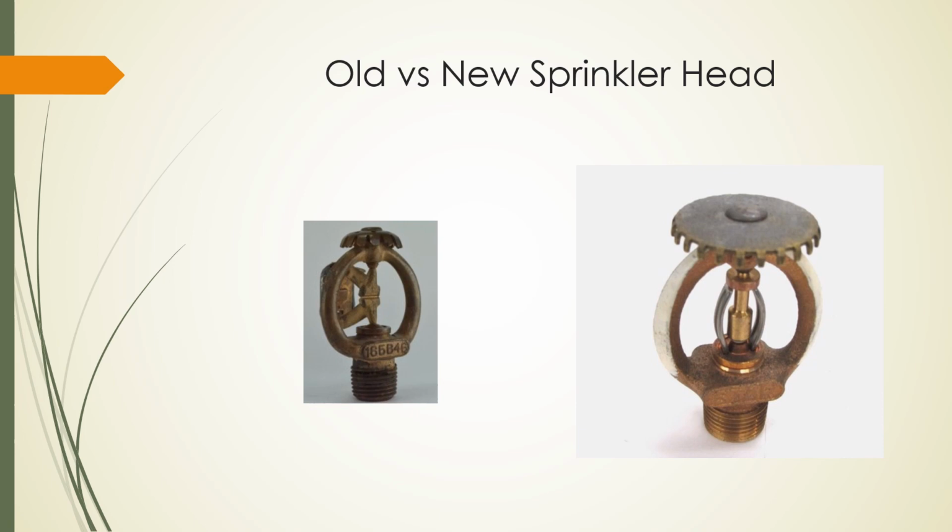So as you can see, there are two sprinkler heads. The one on the left is a 1946 upright star half-inch K 5.6 head. You'll notice that the deflector at the top looks very small. And to the right is a star upright head, date unknown. But you can see clearly that the frame itself looks similar. The fusible link is different types, but it's mainly the deflector type. That's one of the big differences.